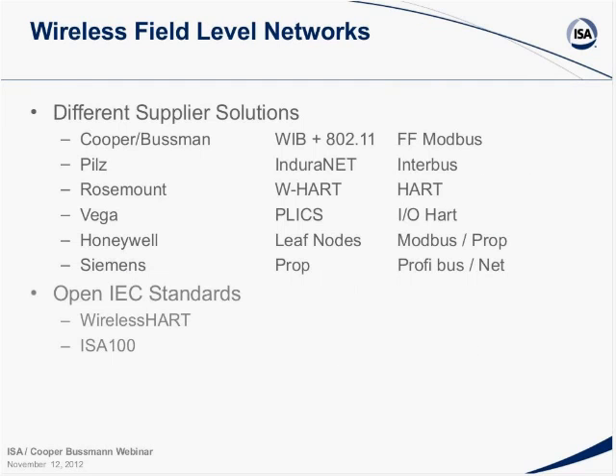So there's the field level, going back to the field level networks. We have different supplier solutions that are proprietary, shown here. Cooper Bussmann, for a number of years, is probably one of the longer serving wireless networks, and they have a network called WIB that also uses 802.11 and also supports Fieldbus, Modbus, and Profibus protocols on that. Then various other manufacturers have their own proprietary protocols. And then we have the open IEC standards: Wireless HART, which is an approved IEC standard, and ISA 100, which is just out for ballot and should be approved very early next year. Both of these protocols have been approved by ANSI, and do have the supporting infrastructure and necessary compliance institutes to confirm they fit with their standards.